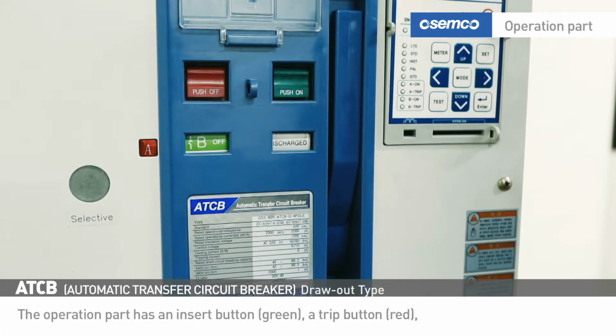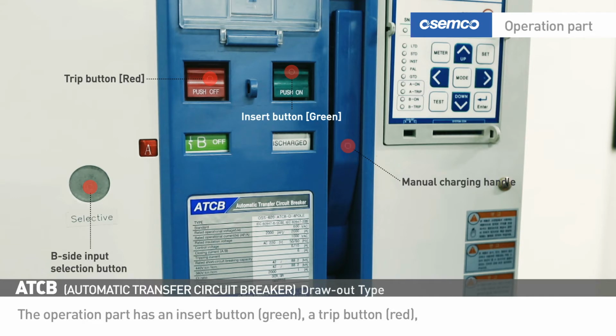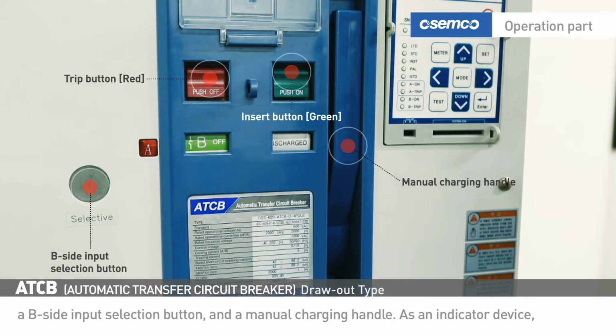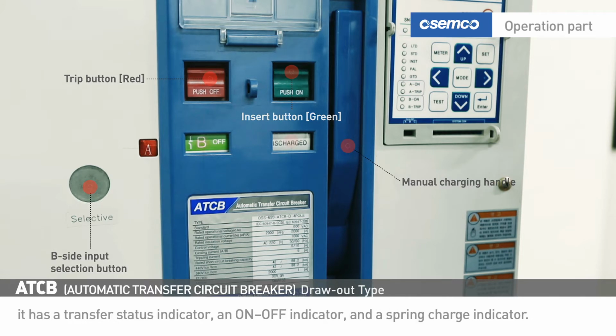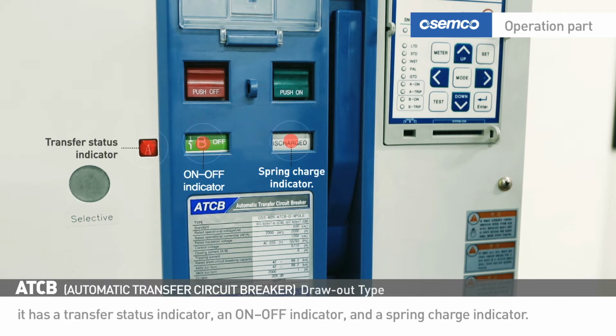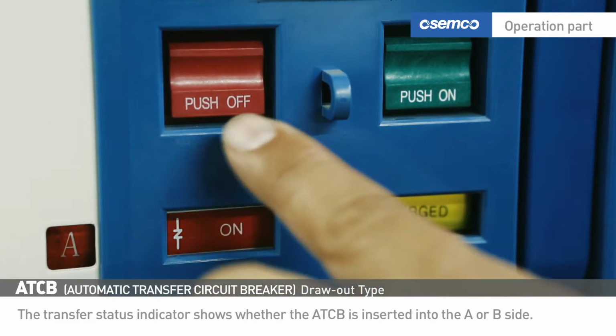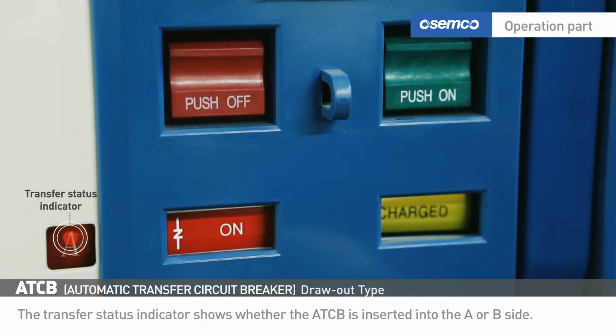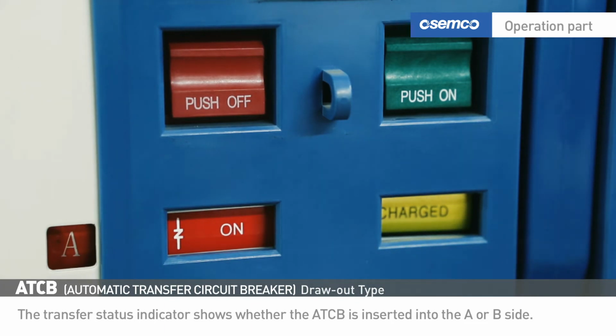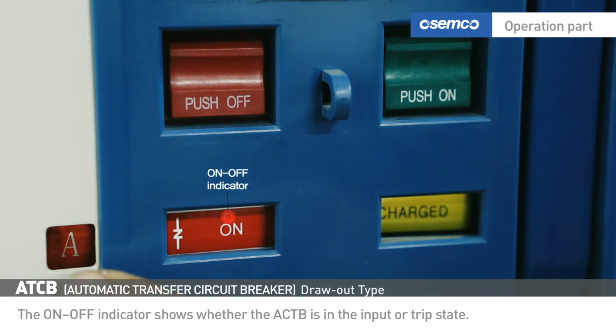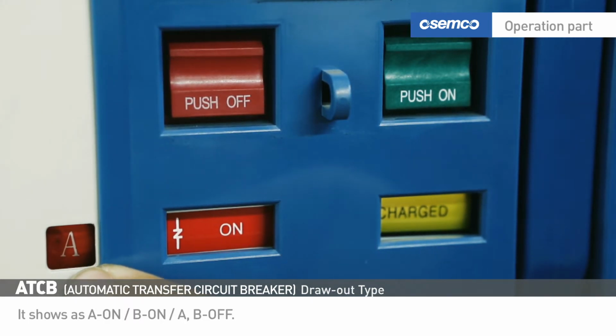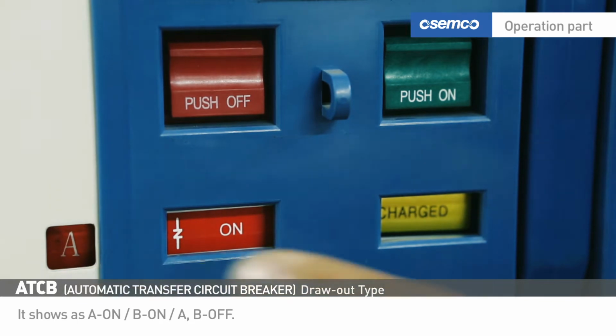The operation part has an insert button, a trip button, a B-side input selection button, and a manual charging handle. As an indicator device, it has a transfer status indicator, an on-off indicator, and a spring charge indicator. The transfer status indicator shows whether the ATCB is inserted into the A or B side. The on-off indicator shows whether the ATCB is in the input or trip state. It shows A on, B on, A, B off.